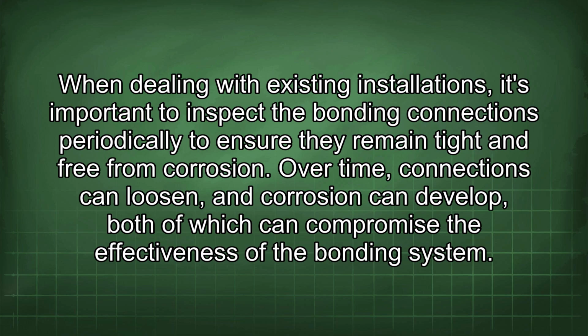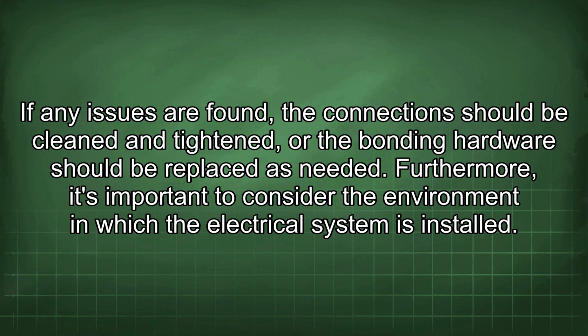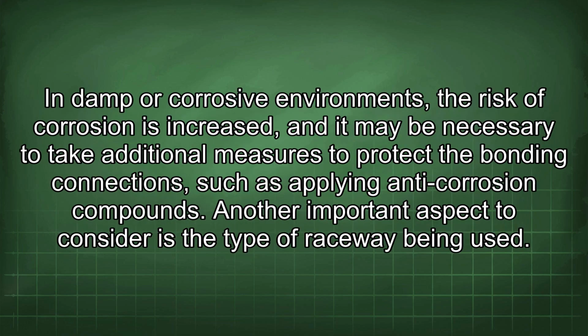Over time, connections can loosen and corrosion can develop, both of which can compromise the effectiveness of the bonding system. If any issues are found, the connections should be cleaned and tightened, or the bonding hardware should be replaced as needed. Furthermore, it's important to consider the environment in which the electrical system is installed. In damp or corrosive environments, the risk of corrosion is increased, and it may be necessary to take additional measures to protect the bonding connections, such as applying anti-corrosion compounds.